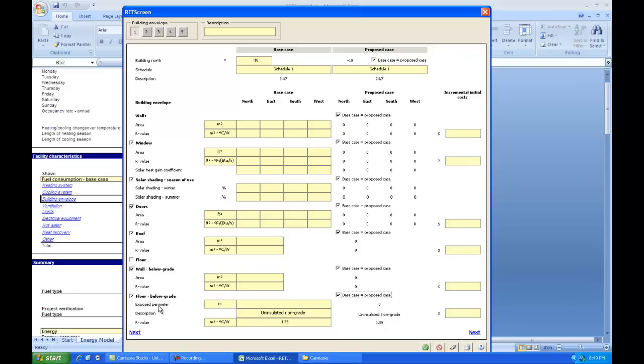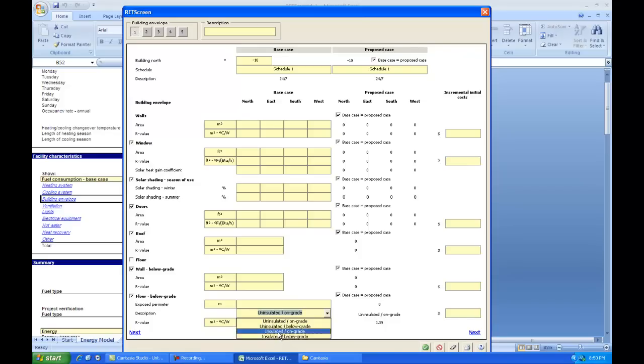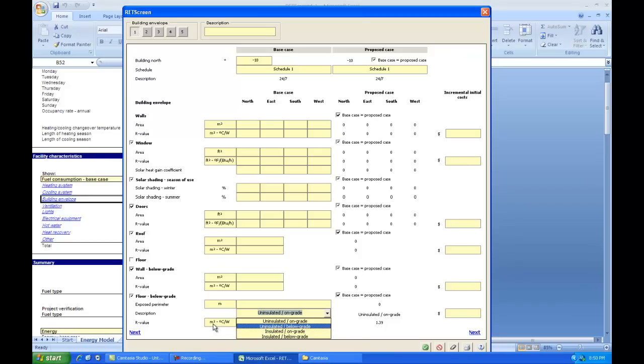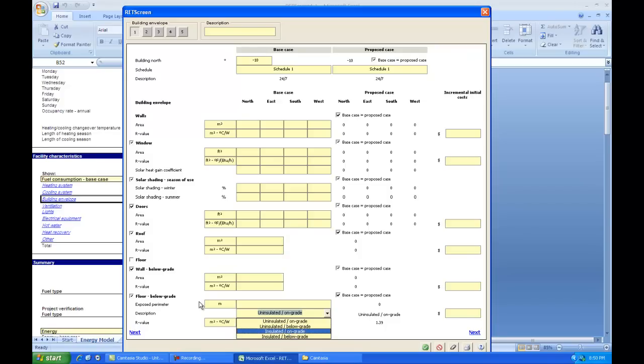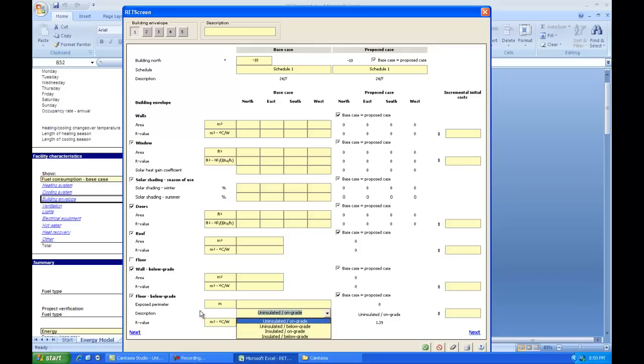So the amount of heat that the floor loses has a lot more to do with how much perimeter it has rather than how much area it has. So a long skinny ranch style bungalow, the floor in the basement would lose more heat than in a nice cubic square building, which would have less perimeter for the same amount of area on the inside. Here we can tell the system what sort of insulation we have going on. It doesn't give us very many choices, just insulated or uninsulated. If we choose insulated, then we can choose the R value of the insulation. And here's where we would go on grade or below grade. So if we build a slab on grade building, we would choose a floor on grade, even though it says below grade up here as a category.